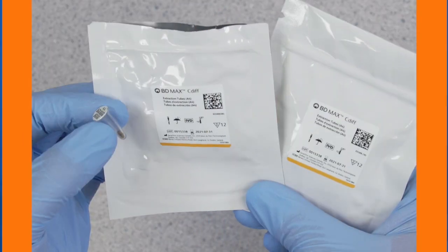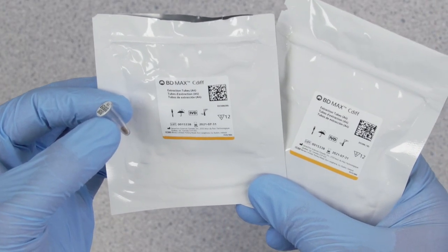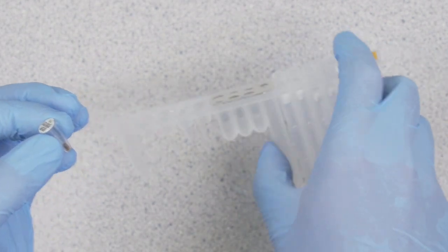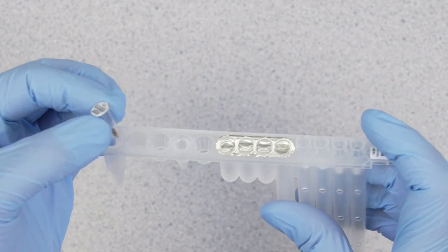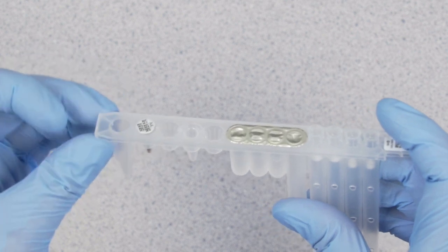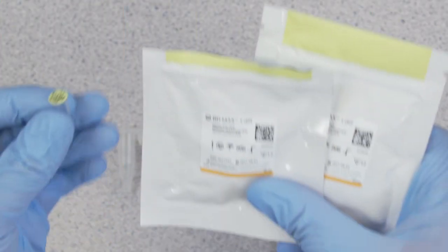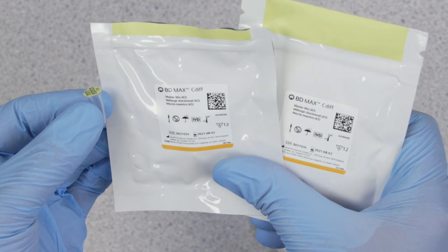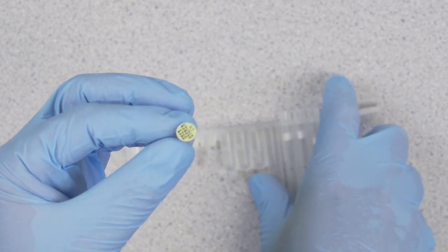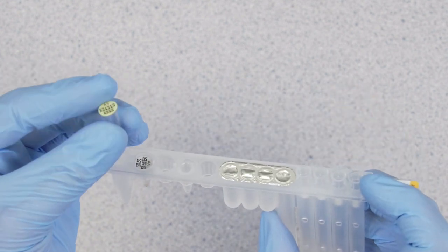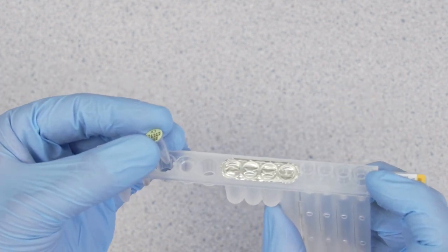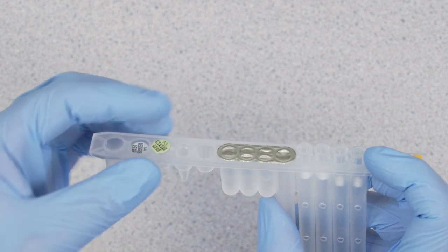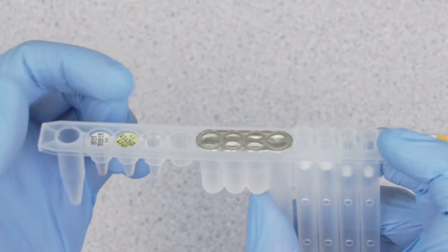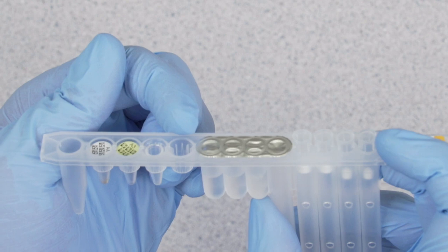The extraction reagent tubes are in 2 resealable pouches and contain DNA magnetic affinity beads, protease reagents, and sample processing control. It is placed in snap-in position 1. The master mix tubes also come in two resealable pouches and contain DNA polymerase, nucleotides, and assay-specific molecular primers and probes, along with sample processing control-specific primers and probes. Single master mix tubes are placed in snap-in position 2. If a second master mix is required, it is placed in position 4.